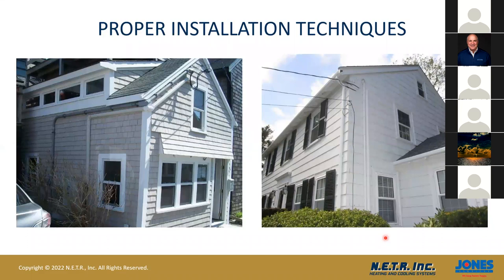And then the proper installation techniques that would go outside. You would have some slim duct or line hide on the outside of the house, and you can see it right here. You can see here's a tan house, tan line hide, white line hide on the side. You can actually see, if you look close enough, there is a unit sitting right here. So nice clean installation, follows the electrical lines. This was a little cottage we did up in Rockport, Massachusetts, up by the water. Here's a white house right here with some white line hide on it. There was a unit in this bedroom. You can see right here, there's some white line hide running down next to the electrical. And if you look close enough, there's another one right here coming out. White on white, looks nice and neat. Doesn't look like the photo that I showed you previously.